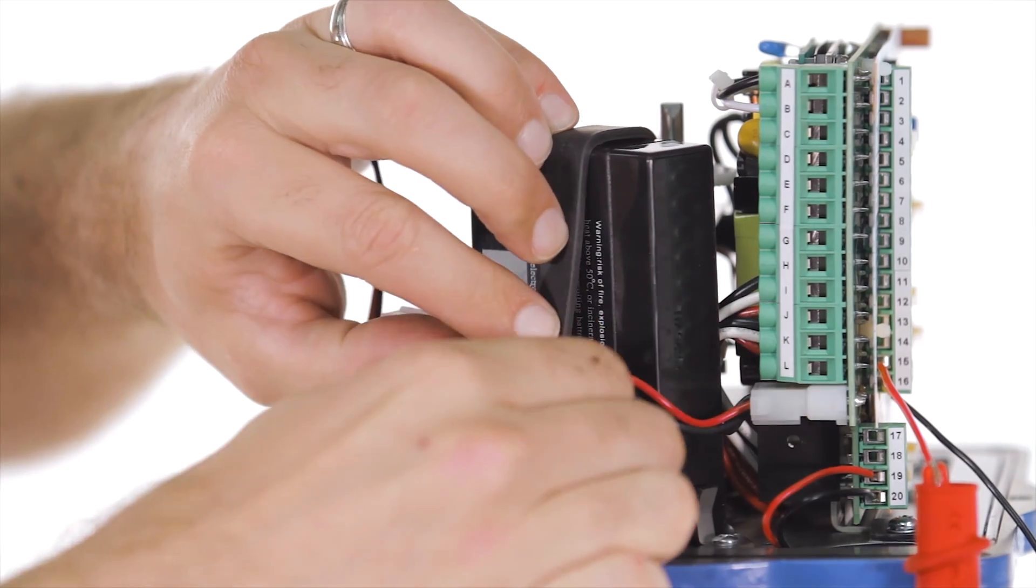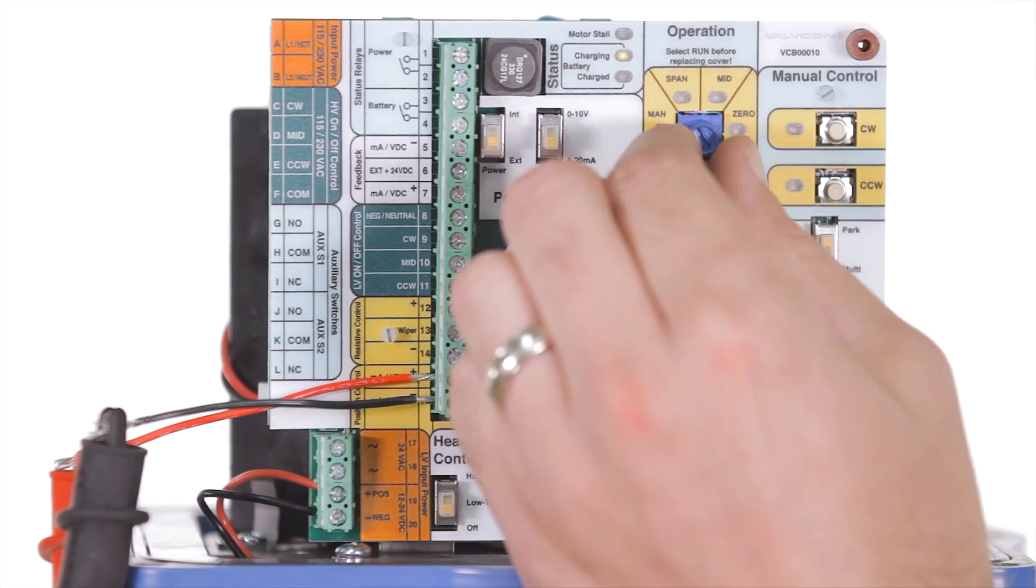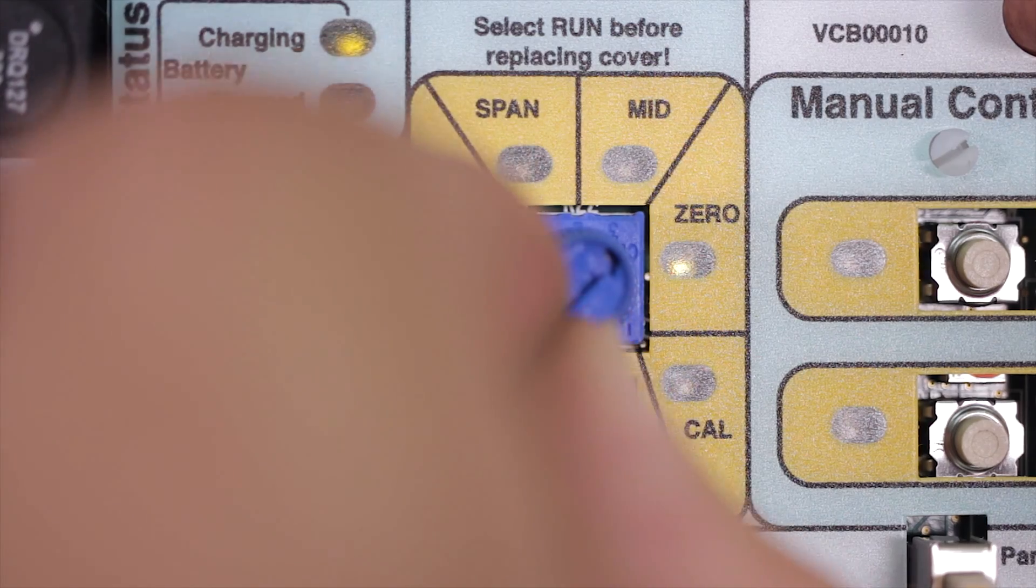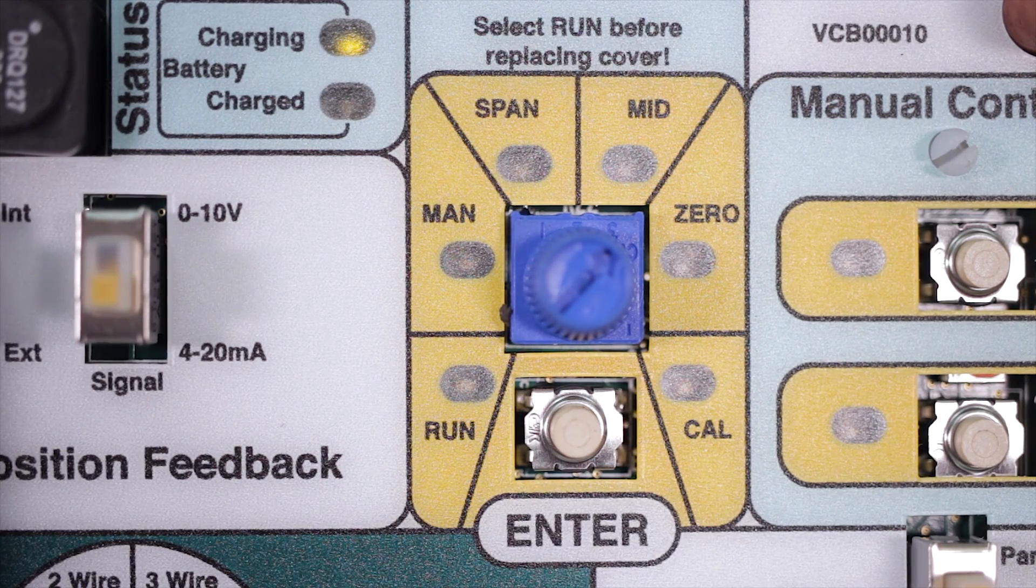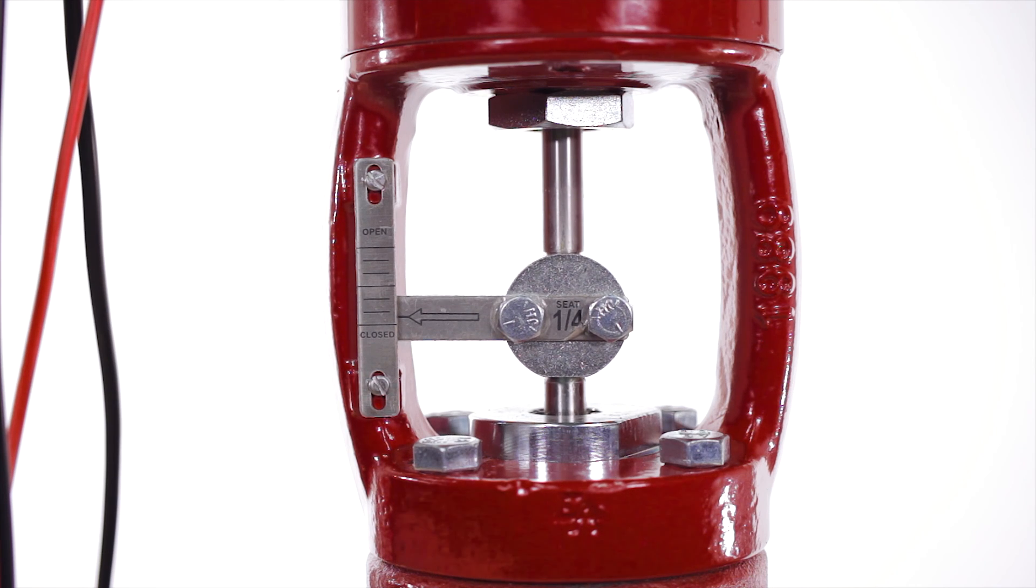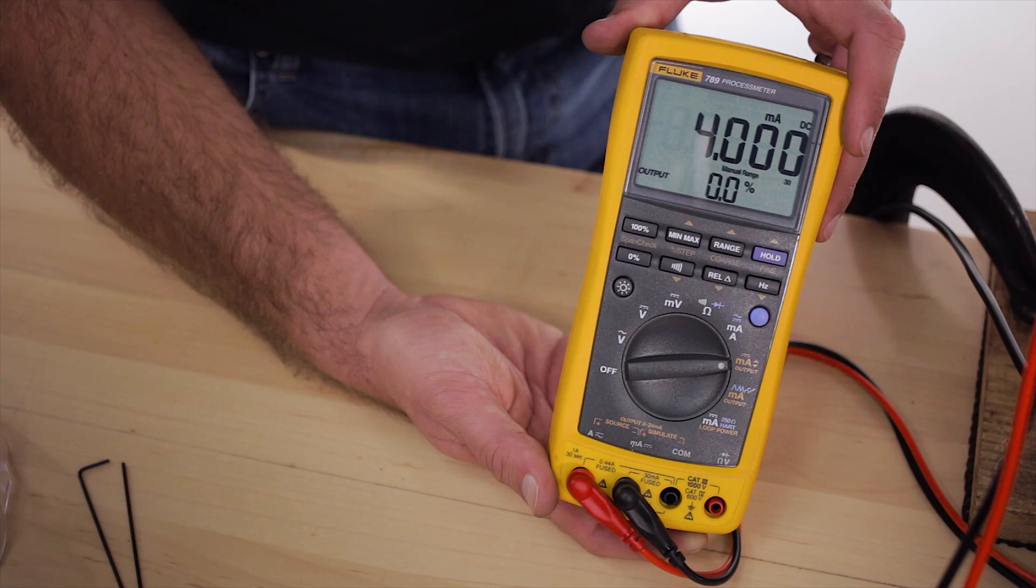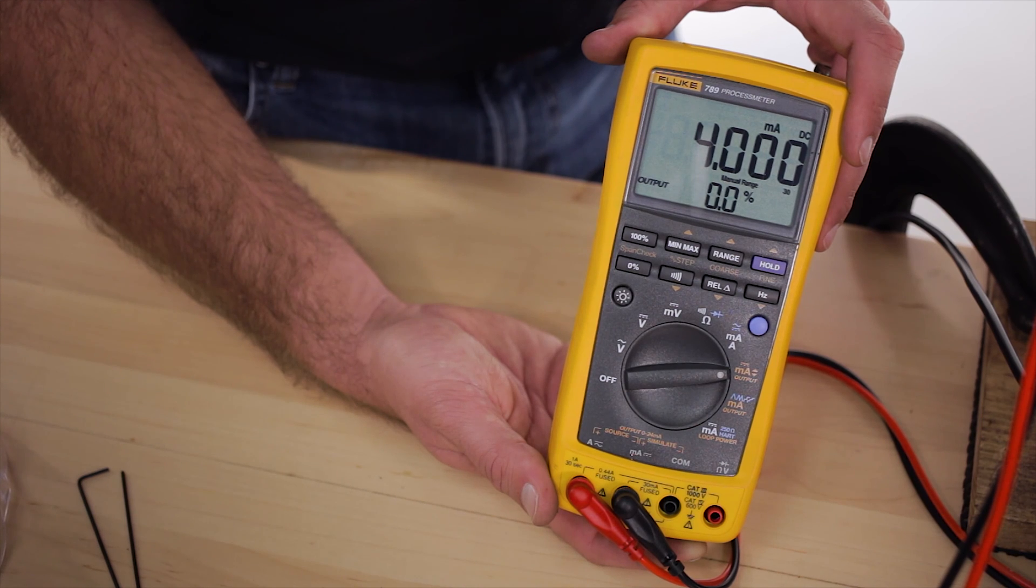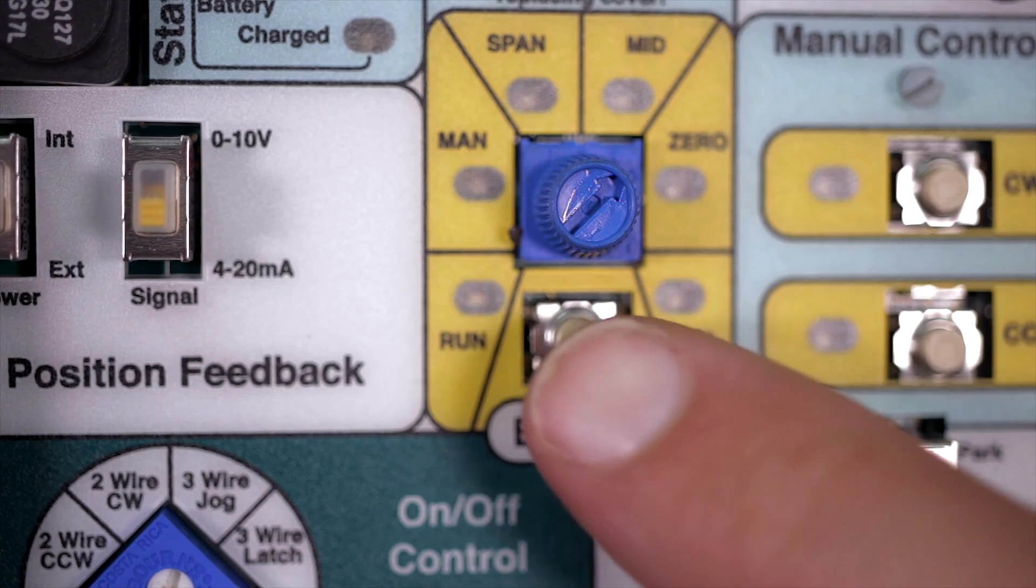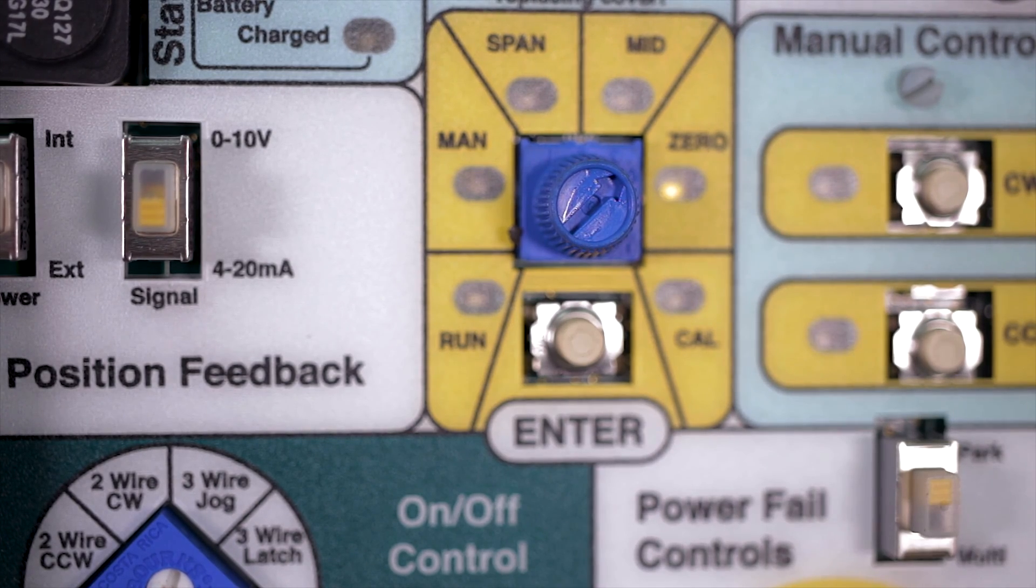Next we'll set your smart limits. Turn your operation mode selector switch to the zero setting and hold the enter button down for two seconds until the LED starts blinking. Run your valve to the fully closed position. Next send a four milliamp signal to the actuator from your loop calibrator. Push the enter button to lock in your fully closed signal.